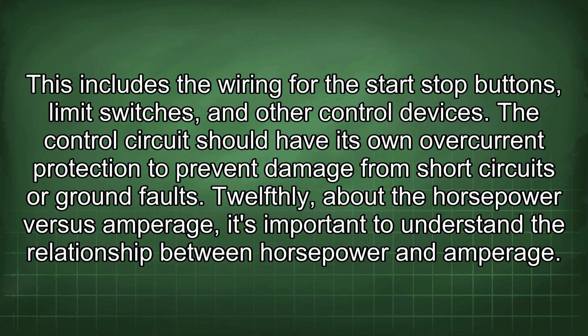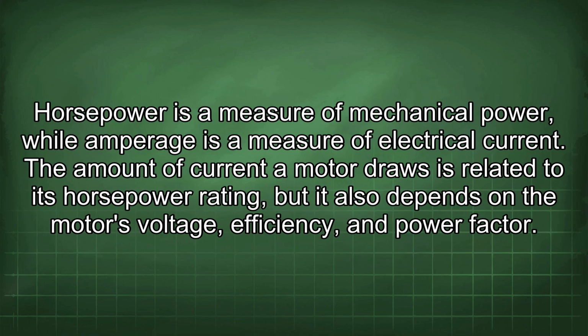12thly, about the horsepower versus amperage. It's important to understand the relationship between horsepower and amperage. Horsepower is a measure of mechanical power, while amperage is a measure of electrical current. The amount of current a motor draws is related to its horsepower rating, but it also depends on the motor's voltage, efficiency, and power factor.